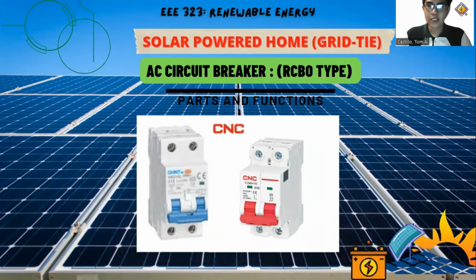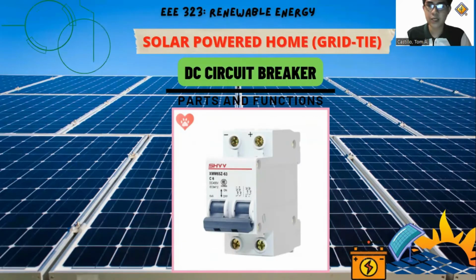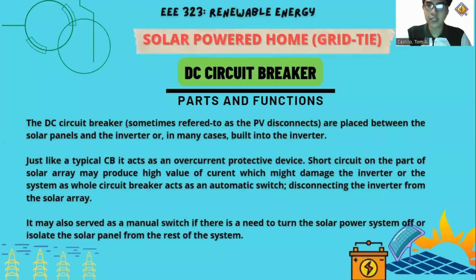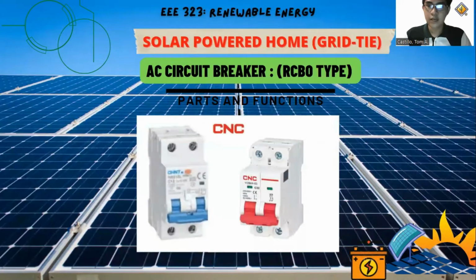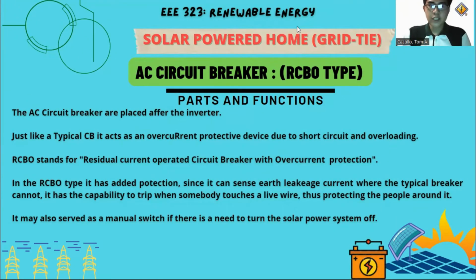The DC circuit breaker is different from the AC circuit breaker of the RCBO type, because this DC circuit breaker, the MCB, has polarity. Then the AC circuit breaker, the RCBO, has a symbol with a sine wave on it. So what is the difference of the RCBO type? The AC circuit breaker is placed after the inverter. Just like a typical CB, it acts as an overcurrent protective device due to short circuit and overloading. So the causes of overcurrent are short circuit and overloading.